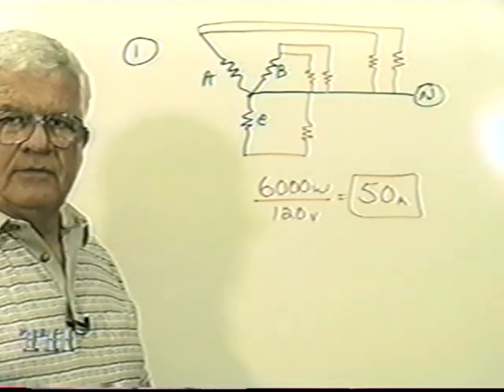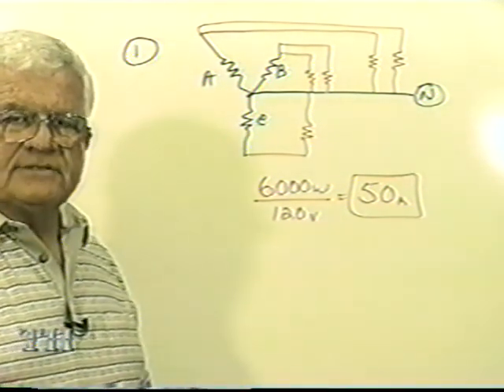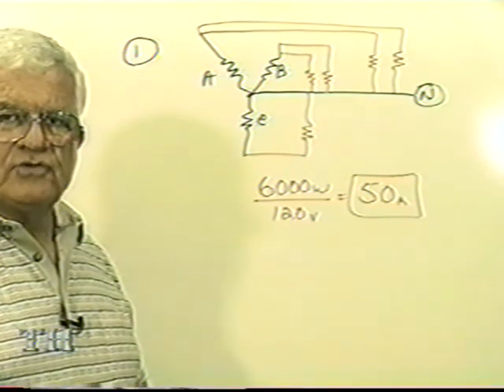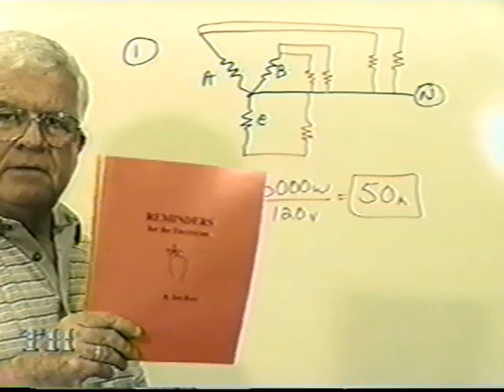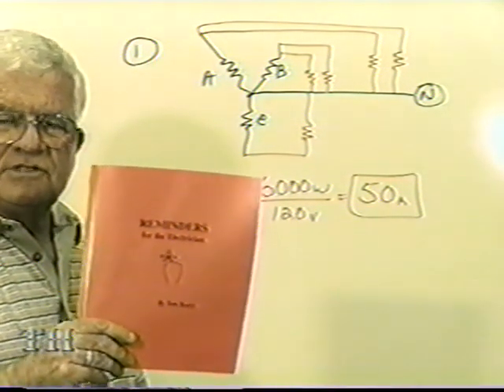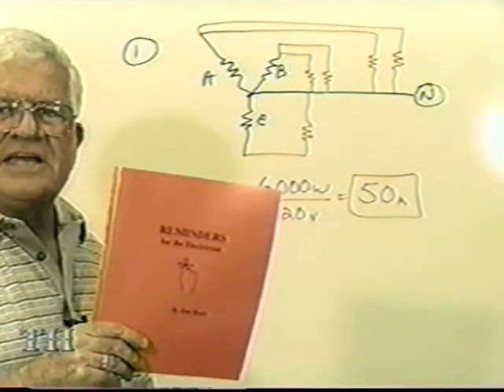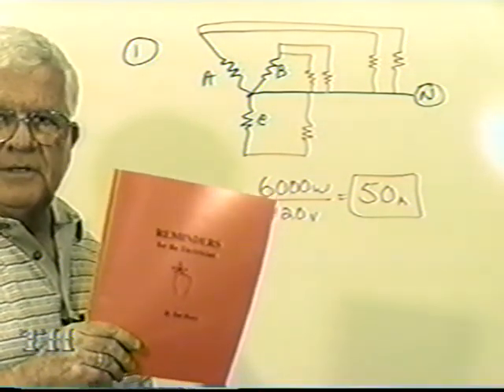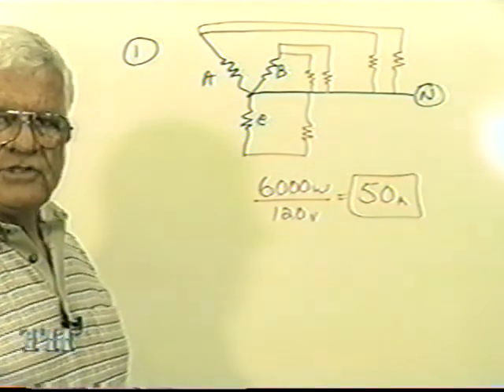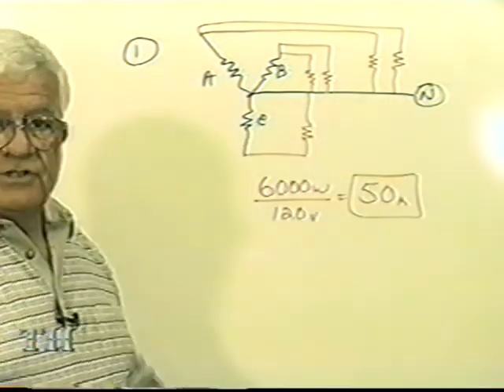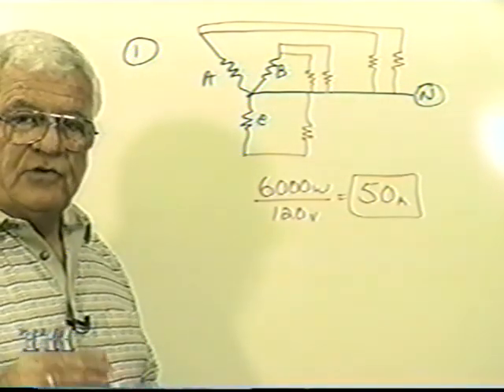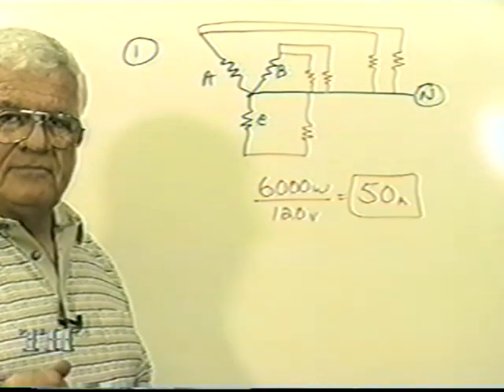In question 1, the answer is 50 amps. It's called the unbalanced Y on a neutral. What I'd recommend, in this reminders book which is pre-drilled to fit in your loose leaf, on page 50 there's a formula showing you how to calculate. But what you're doing is taking the largest load, and the neutral would have to carry that maximum current, 50.